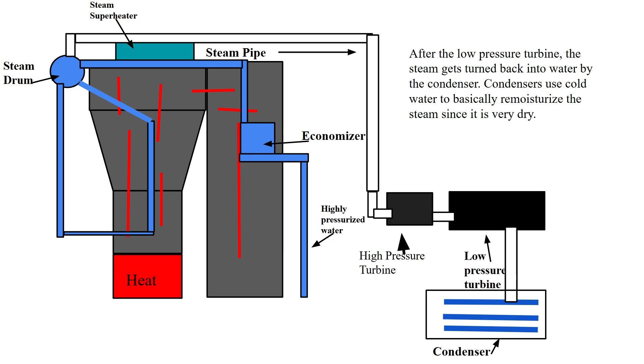After the condenser, there's a feed water pump, which is a multi-stage centrifugal pump that uses centrifugal force to increase the pressure, because there are multiple discs inside that spin and increase the pressure of the water, making it flow more smoothly.